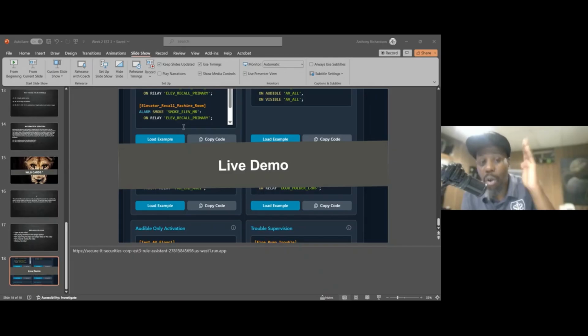Pretty much we're going to turn all of the speakers on for this entire building. We're going to turn the messages on. So once we turn the amp on, once we turn the speakers on, now we turn the messages on so that the message can go through the speakers. These are the pre-recorded messages like alarm, go to the stairwell, this is just an emergency, this is not an emergency, or get out of the building. Whatever the message is, you can pre-record that inside the audio.